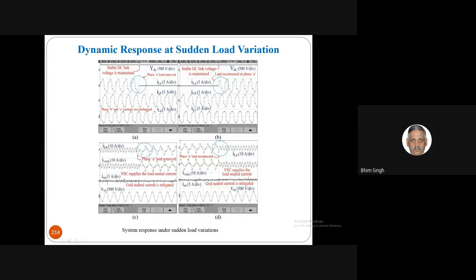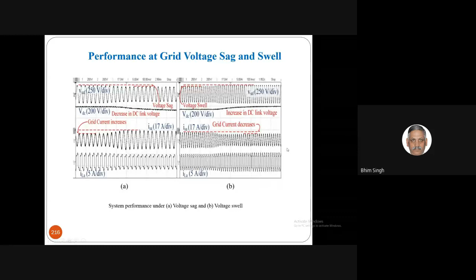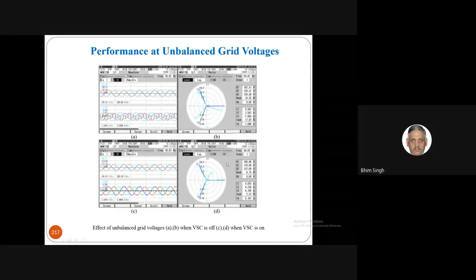And you can think about the power, because it is a two-stage system, so we are able to take care of the DC link voltage, an adaptive DC link voltage for reducing the losses, which I have mentioned earlier, under voltage sag and swell conditions also. That reduces the losses, and you get around a couple of percent extra generation under those voltage varying conditions.